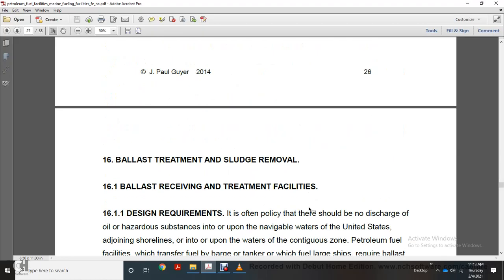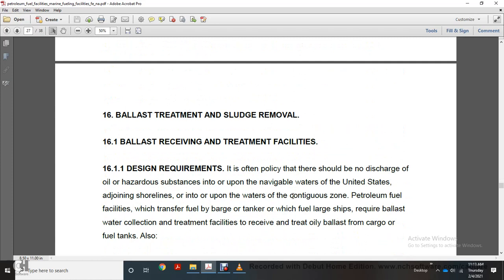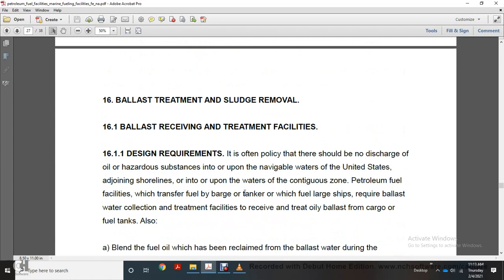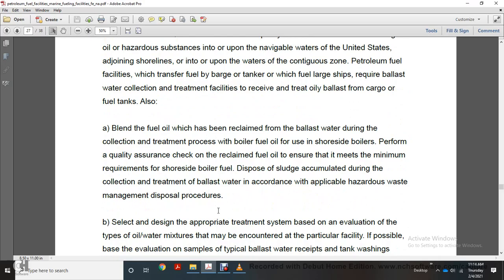16. Ballast treatment and sludge removal. Ballast receiving treatment facility design. It is the policy that there should be no discharge of hazardous substances into navigable waters of the United States, adjoining shorelines, or upon the waters of the contiguous zone. Petroleum fuel facilities that transfer fuel to barges, tankers, and large ships require ballast water collection and treatment facilities to receive oily ballast from cargo and fuel tanks. Blended fuel can be reclaimed from the ballast water during the collection and treatment process, with boiler fuel for a shoreside boiler.